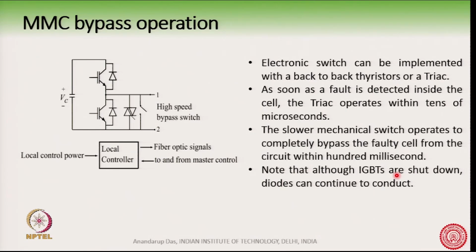Once this is done, this is somewhat done in the local controller. Remember that all these MMC cells have a local controller. There is a main controller which controls all the cells, but for each cell there is a local controller, which is usually at the same point. The cell has an enclosure, and inside the enclosure also sits this local controller.